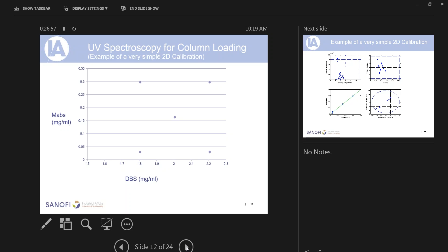But I wanted to show you that the calibration has a 5-point calibration, but it's shaped like a square with a center point in it. And this is effectively how you would build a 2D calibration. It requires 5 data points. If we move on to the next slide, then we take these spectra. This is a whole bunch of statistical charts for PLS. The one that's of interest is the graph at the bottom left-hand side that just shows a calibration curve. So here we are quite capable of measuring MABs in a concentrated mixture of other protein quite reliably.